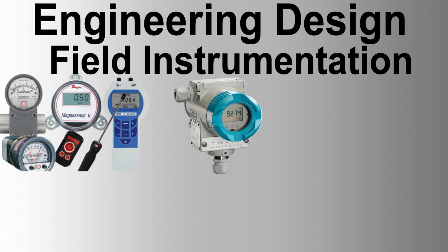Thermowells, 2 inch flanged for class 900 and lower. DP type level transmitter, 2 inch flanged. Level gauges, magnetic. Level transmitters, guided wave radar type, 2 inch flanged on standpipe. Level transmitter, radar ultrasonic type, 4 inch or 6 inch flanged depending on application. Level switches, 2 inch flanged minimum. Standpipes, 2 inch flanged. Orifice with flange taps, 1/2 inch NPT, flange taps.